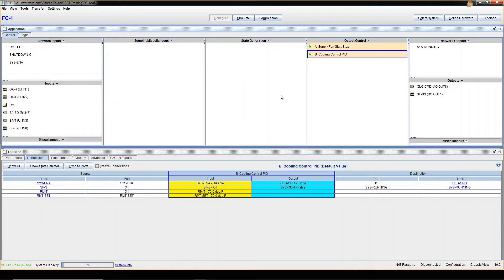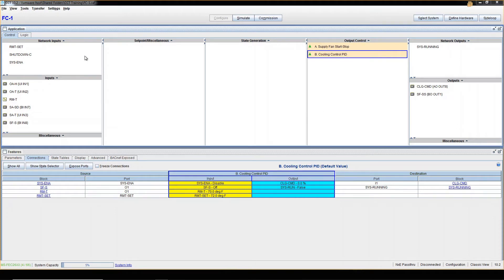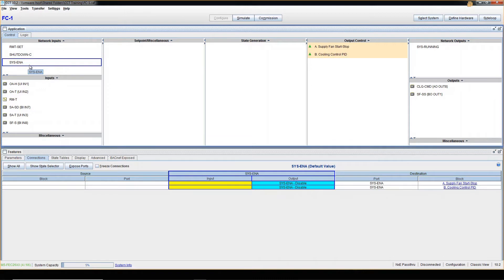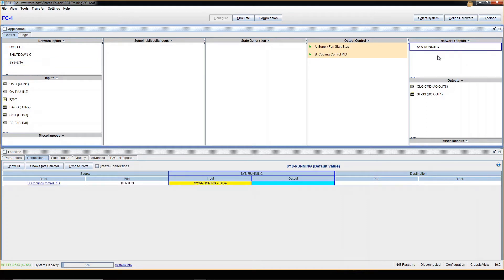The idea of this tutorial is to show you how to identify them and know the differences. Let's start with network inputs and network outputs. As the name implies, these are not real physical inputs — these are software inputs. For example: room temperature setpoint, shutdown command, and system enable are all software values. For network outputs, we have something like 'system running,' which is a status indicating the system is actually running.